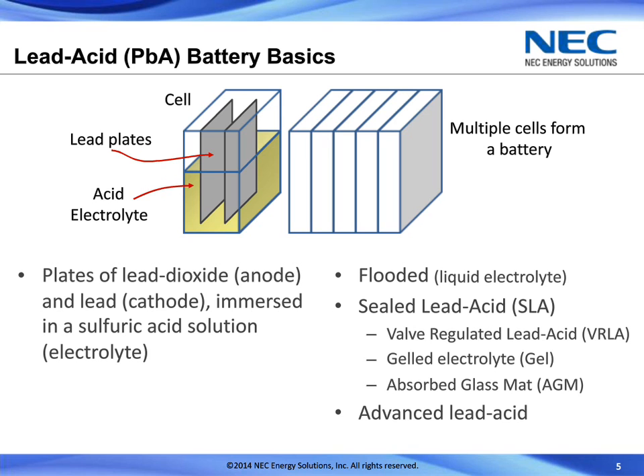So the big batteries that we may all be used to in larger installations, and even in the old days of our automobile, would be the flooded, liquid type electrolyte, which has certain characteristics, but one of those is that you have to maintain them, maintain the water, and avoid any kind of spillage that might be associated with them. The more popular batteries today, particularly in the applications that we're exploring today, are sealed lead acid batteries that use a valve, or sometimes called a valve-regulated lead acid battery.